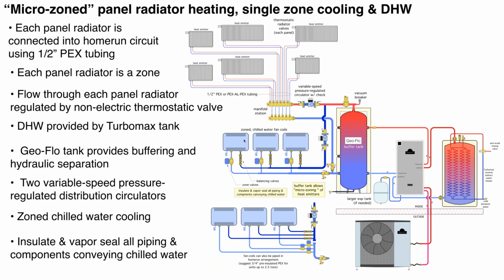Critical thing, make sure any fan coils that you intend to use for chill water cooling are equipped with drip pans. And you'll see I've shown a drain coming out here with a trap. These are going to produce condensate, and that condensate has got to be routed either outside or into some type of a drainage system. Never use a fan coil that was just set up for space heating in a chill water application. So how are we creating flow? Well, we're using another variable speed pressure regulated circulator. We've got zone valves shown on the individual fan coils. In this case, I'm showing the zone valves implying that they're out near the fan coil. In some cases, these zone valves are actually built right into the fan coil units.